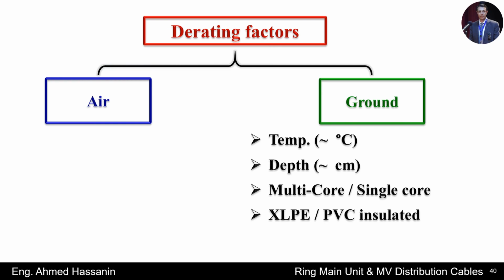I will talk about the importance of the derating factors to calculate the thermal current of these medium voltage cables or any electrical power cables in general. In addition, I will explain the factors that are related to the thermal current calculations, like ground temperature, cable depth, multi-core or single-core cables, and whether the insulation of the cable is cross-linked polyethylene XLPE or PVC insulation.